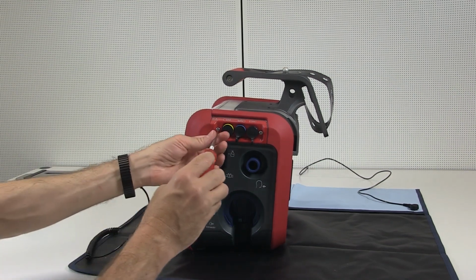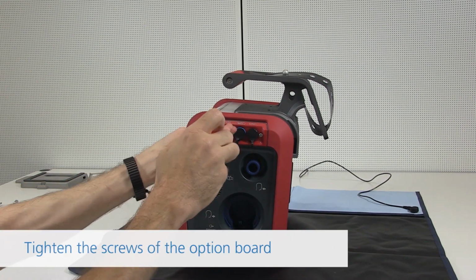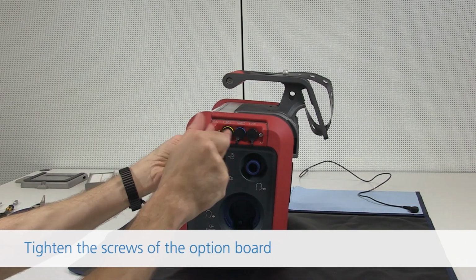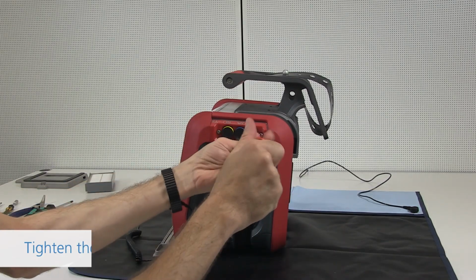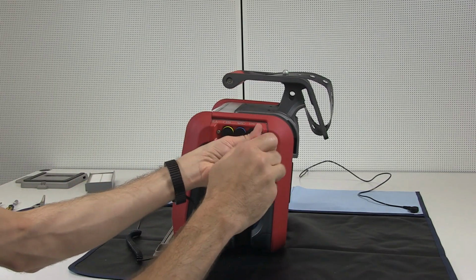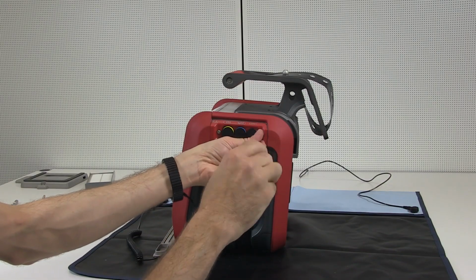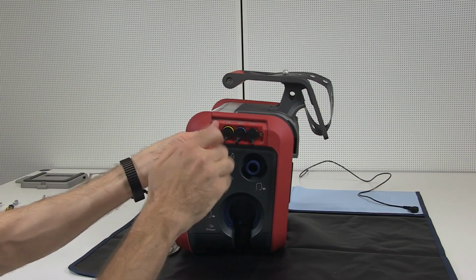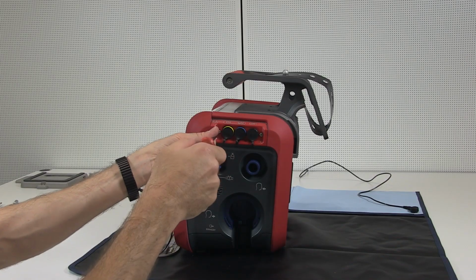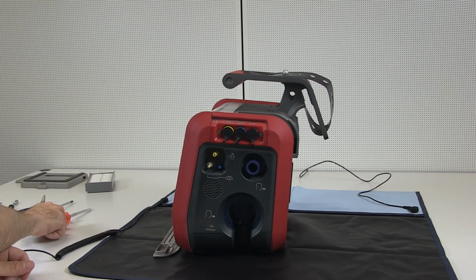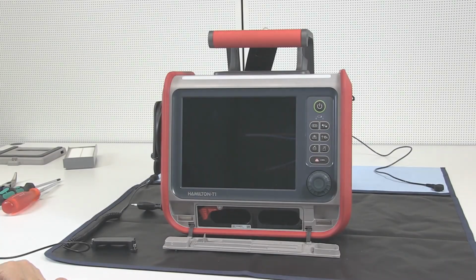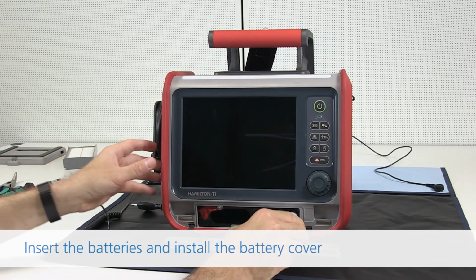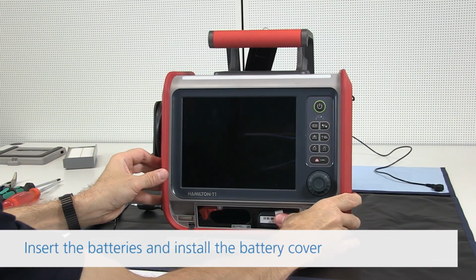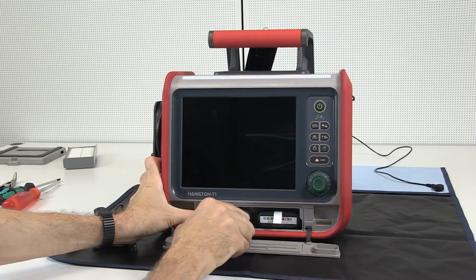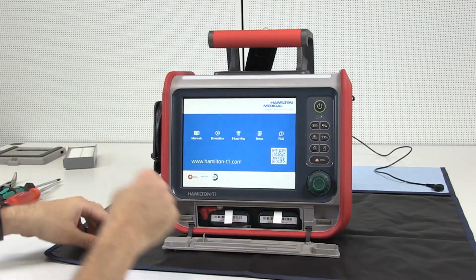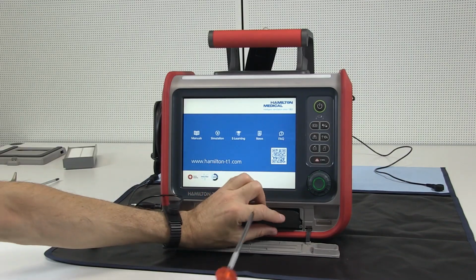Tighten the 2 screws on the option board or option board blanking cover. Install the 2 batteries in the battery compartment, then install the battery cover on the right side battery. Note that the ventilator will start up as soon as you insert a battery.